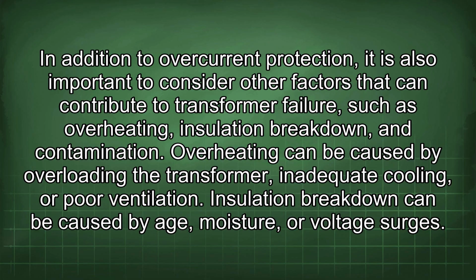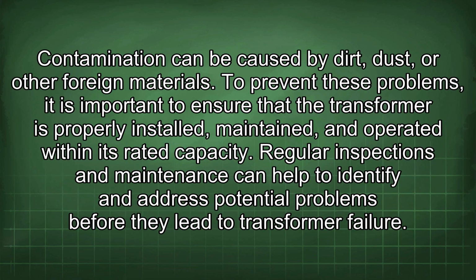Overheating can be caused by overloading the transformer, inadequate cooling, or poor ventilation. Insulation breakdown can be caused by age, moisture, or voltage surges. Contamination can be caused by dirt, dust, or other foreign materials. To prevent these problems, it is important to ensure that the transformer is properly installed, maintained, and operated within its rated capacity. Regular inspections and maintenance can help to identify and address potential problems before they lead to transformer failure.